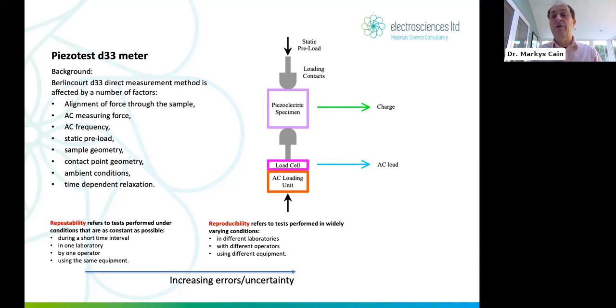So we have two samples, one on top of the other, experiencing the same force. If we know the piezo coefficient of the bottom one, by measuring the voltage integration of charge across an op-amp, we can compare the piezo response by comparing the voltages dropped across the sample under test, the device under test, and the bottom calibration sample. And of course, it works. And it's really convenient because you don't really need a load cell. But there are issues with that, which we'll come on to in a minute.